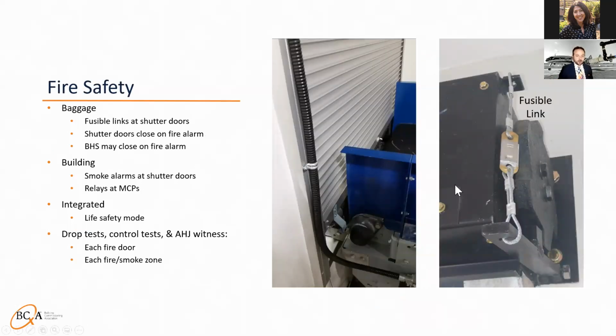In the case of a smoke event in the building, baggage handling fire doors, often you'd want to flush the conveyor underneath and then start closing the door under control. An older way of doing this would be to have a relay at each fire door, but then the fire door itself will just be forced closed. And if there's something underneath, it'll get squished and the door won't close on its own.